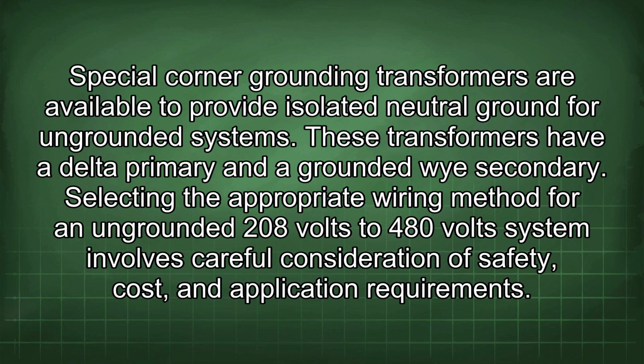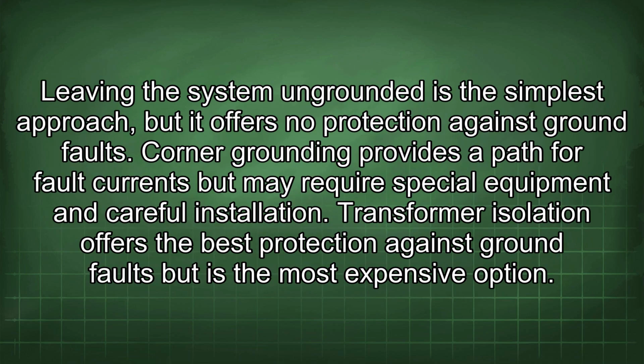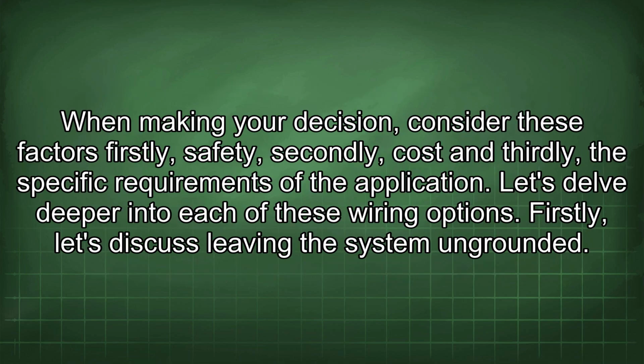Selecting the appropriate wiring method for an ungrounded 208 volts to 480 volt system involves careful consideration of safety, cost, and application requirements. Leaving the system ungrounded is the simplest approach, but it offers no protection against ground faults. Corner grounding provides a path for fault currents but may require special equipment and careful installation. Transformer isolation offers the best protection against ground faults but is the most expensive option. When making your decision, consider these factors: firstly, safety; secondly, cost; and thirdly, the specific requirements of the application.